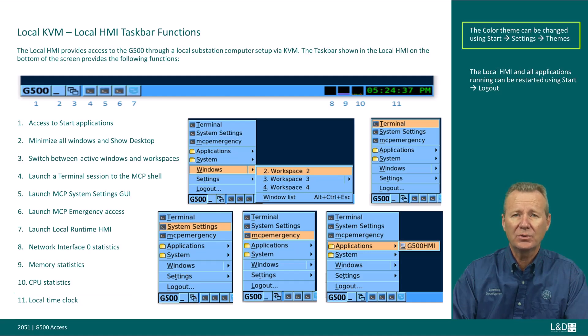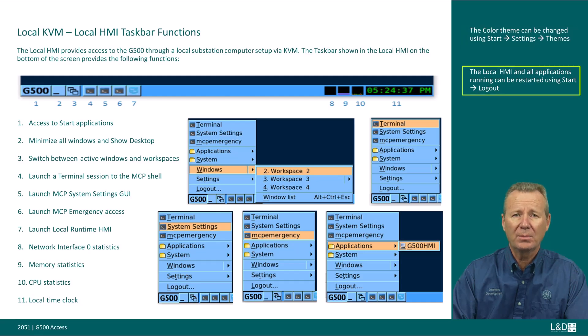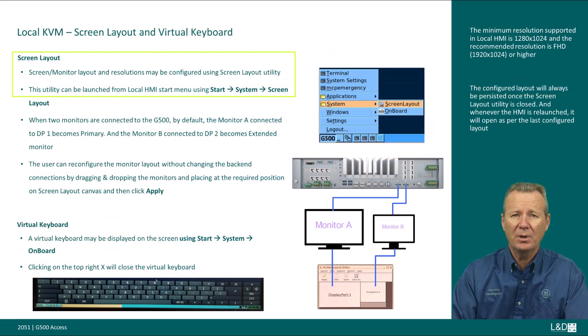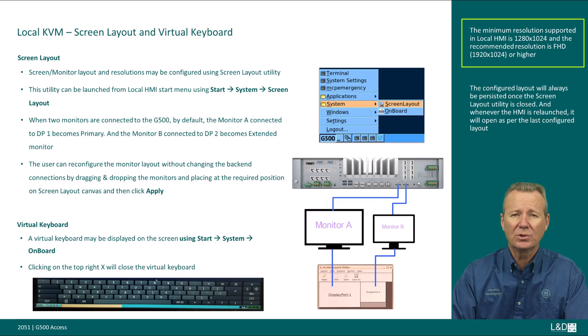The color scheme can be changed using Start, Settings, Themes. The local HMI and all applications running can be restarted using Start, Logout. Screen layout and resolutions may be configured using the screen layout utility. This utility can be launched from the local HMI start menu using the selection Start, System, Screen Layout. The minimum resolution supported is 1280 by 1024 and the recommended resolution is FHD 1920 by 1024 or higher.